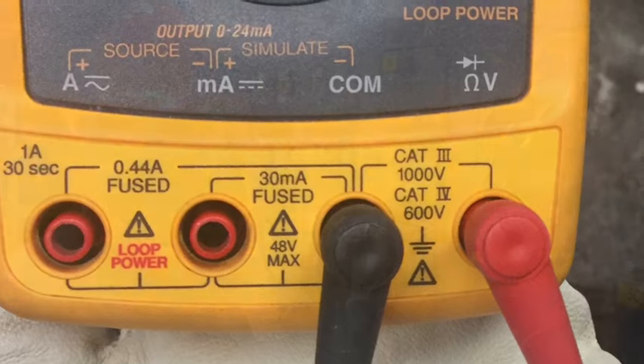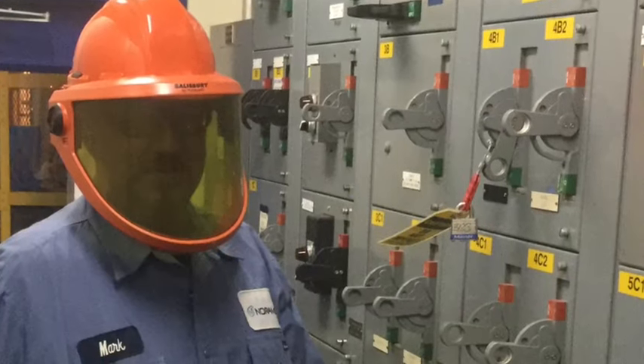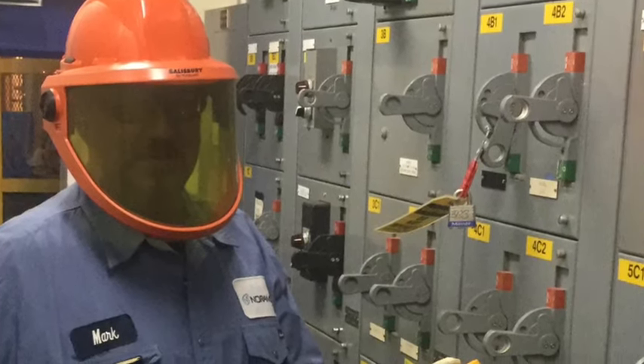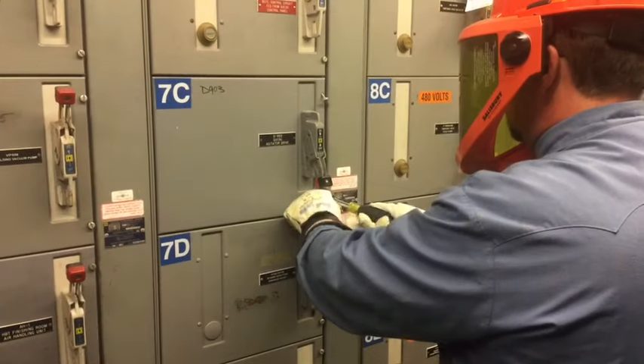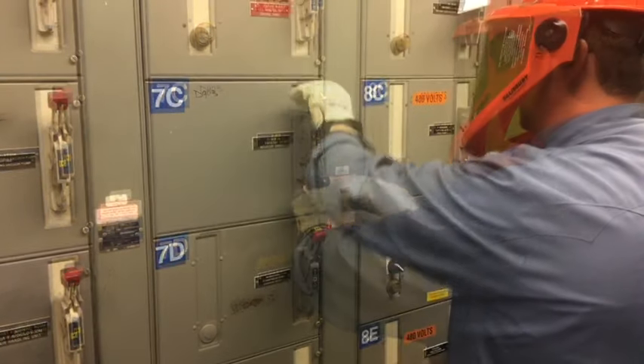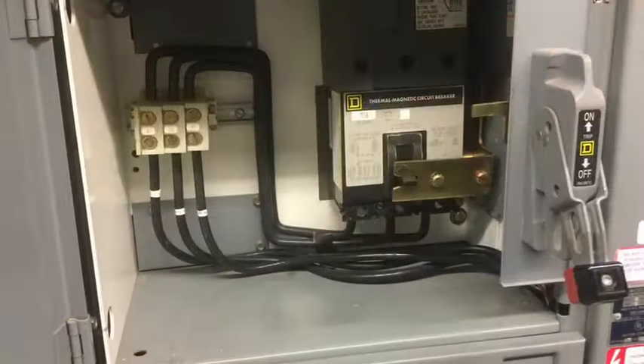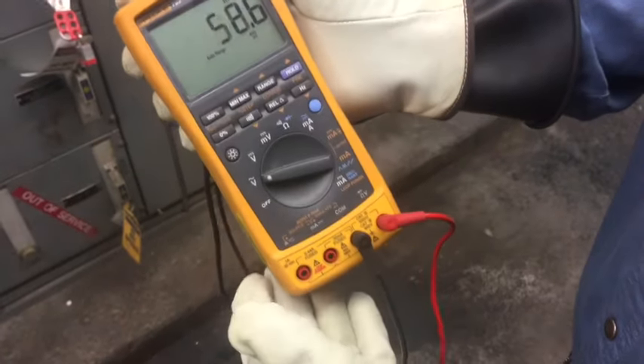Check the PPE and test equipment for calibration dates and voltage categories. Also ensure your PPE is ready for the task at hand. Remove or open covers to expose the components and become familiar with the location of the test points. Set up test equipment to be used.